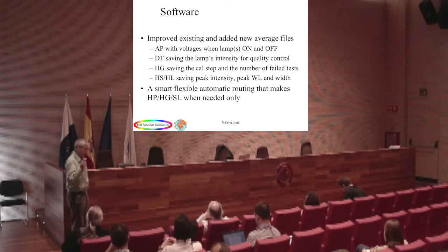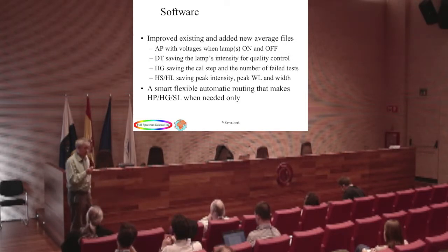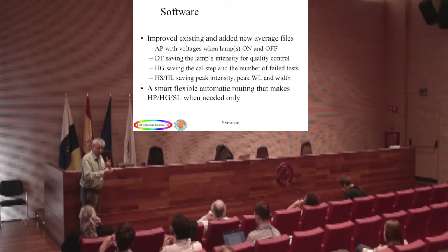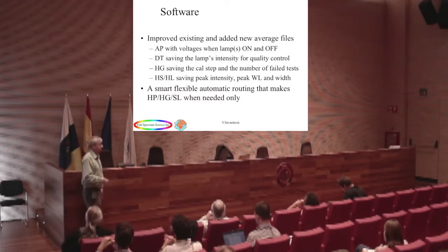We also have some new diagnostic tests, so that again, if something is not quite right or you don't understand, you can run a diagnostic that will potentially discover what is wrong with the instrument, because it moves just about every motor that is possible to move in the Brewer, and tries to understand whether or not it's moving the way you expect it to move.